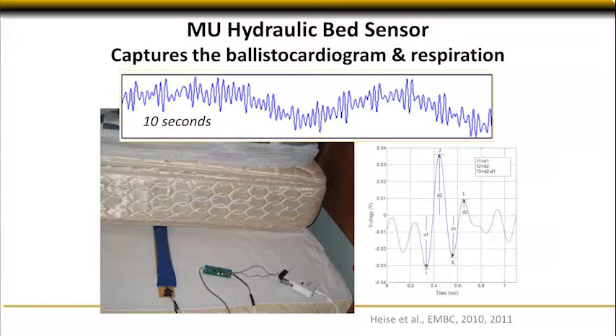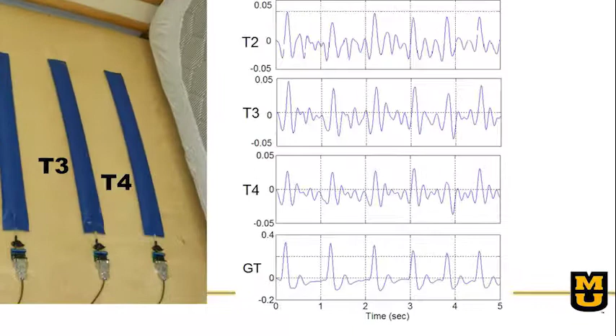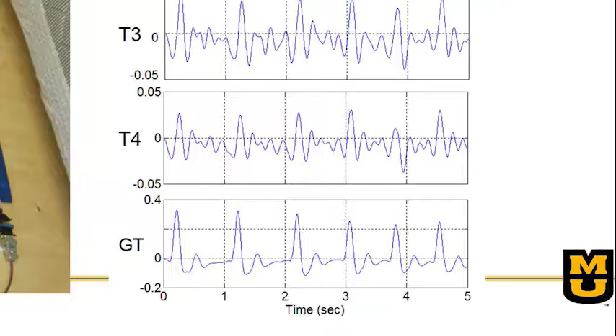As we've continued to work on this, we've now got a system that uses 4 transducers aligned vertically, and we place 4 of them across the bed. They go underneath the mattress, so they're completely non-invasive. We have the signal here that includes a ground truth signal, which would be from a finger sensor. We've done this to test out the bed sensor, where you have somebody put on a finger sensor to see what the heartbeat, what the pulse rate is.